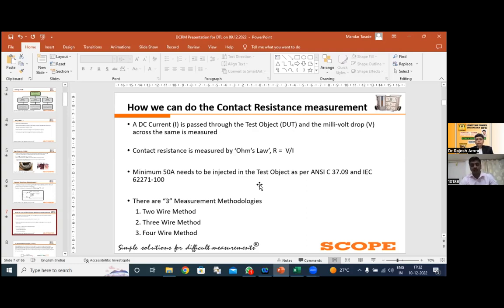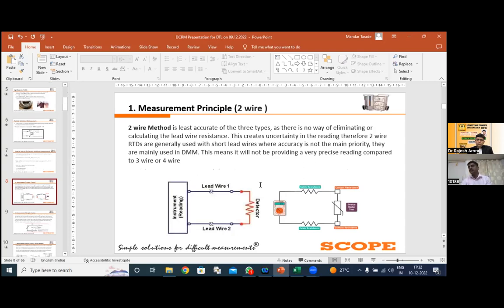According to that, there are basically three measurement methodologies: the 2-wire method, the 3-wire method, and the 4-wire method. In the 2-wire method, the same cable used for injecting the current is used for taking the voltage drop across the DUT. But this method is not very accurate because the lead resistance is not eliminated or compensated. The classic example is the multimeter, where with two cables and a battery we can test an unknown resistance. But here, one thing I want to highlight is that the resistance value must be on the significantly higher side.